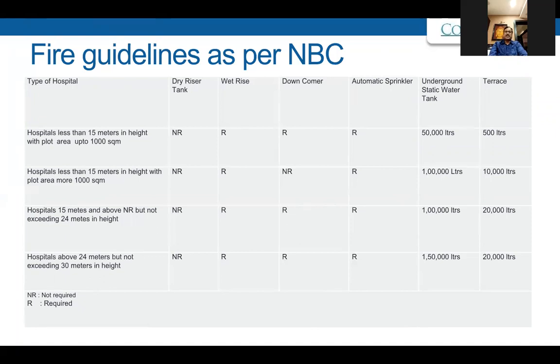For example, you can see in front that you have a dry riser, wet riser, then you have sprinklers. All these are recommended by fire authorities also. And you require an underground static tank as well as a tank on the terrace. So different categories have been identified. Under 15 meters, if the building's area is more than 1000 square meters, then there are slightly different regulations. Then there is also a category from 15 meters to 24 meters. And there is a category above 24 meters, that is high-rise buildings, which have multiple requirements.